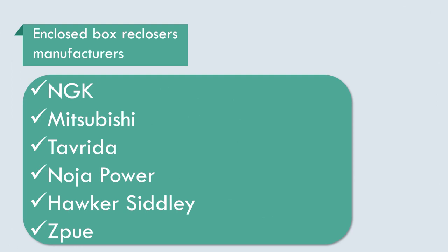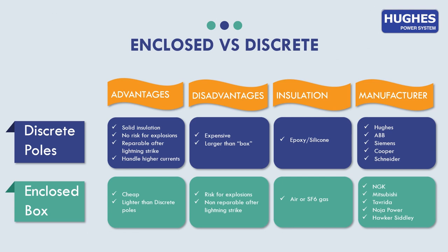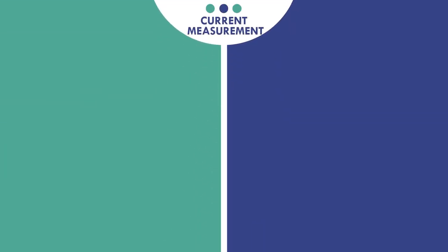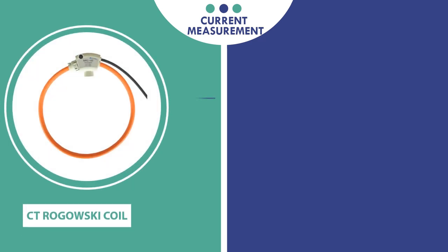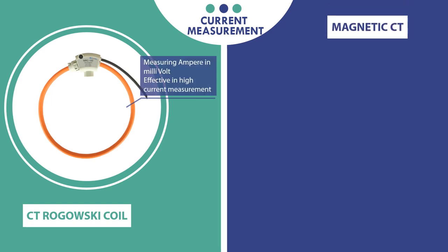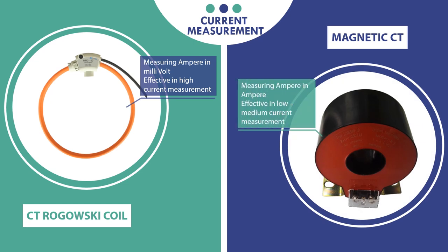Let's move to the second important factor when choosing a right recloser: current measurement device. Here we have two types. Rogowski coil current transformer which measures ampere in millivolt and is effective in very high current measurement. And magnetic current transformer which measures ampere in ampere and is effective in low and medium current measurement.